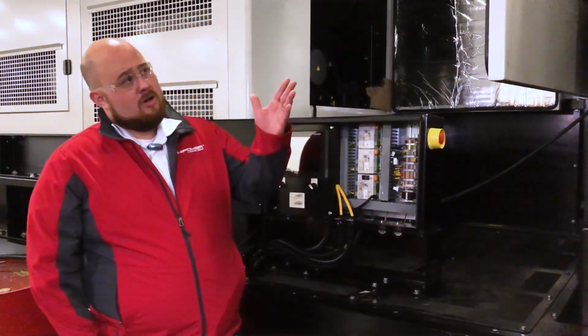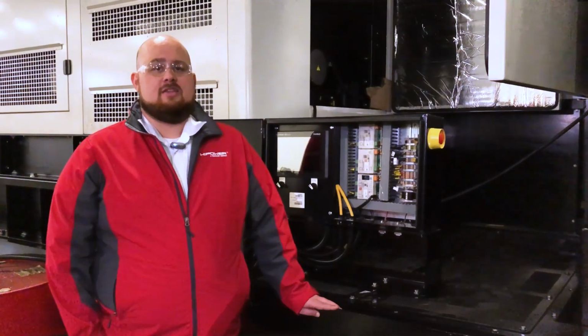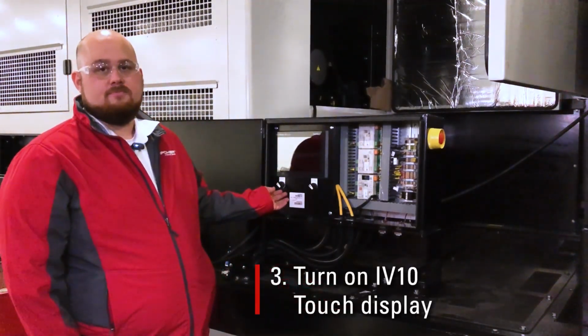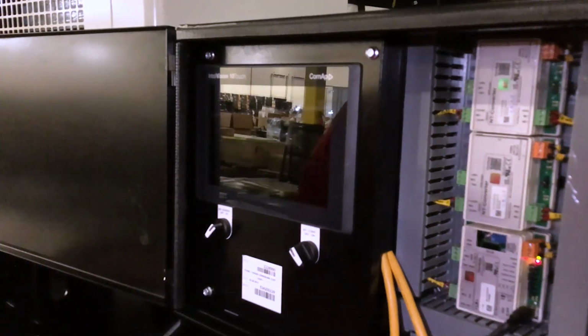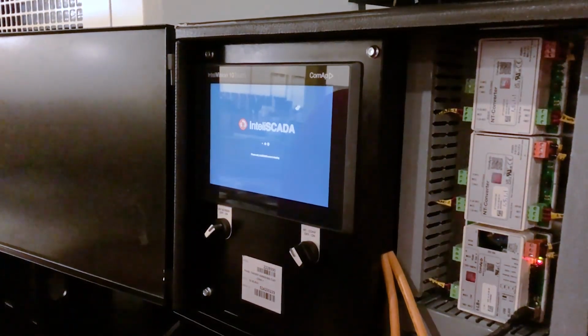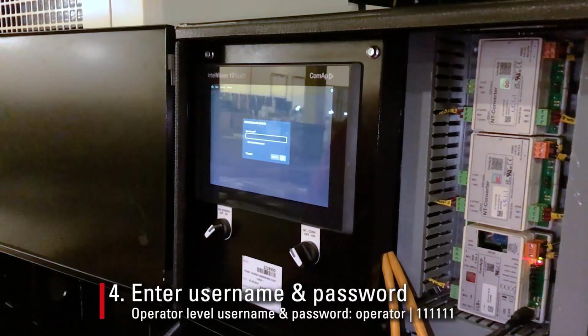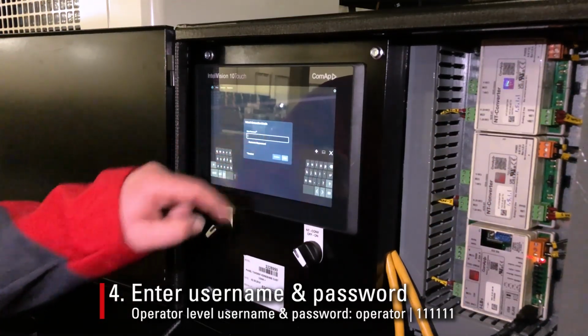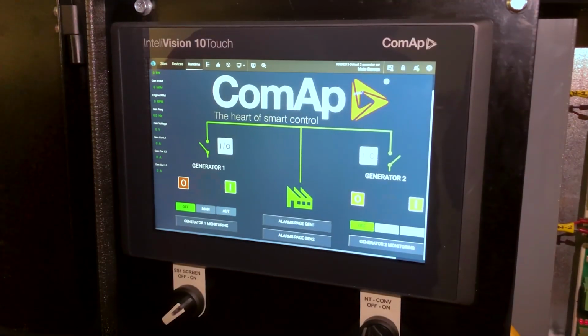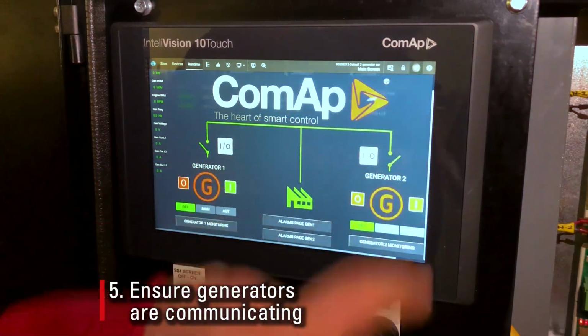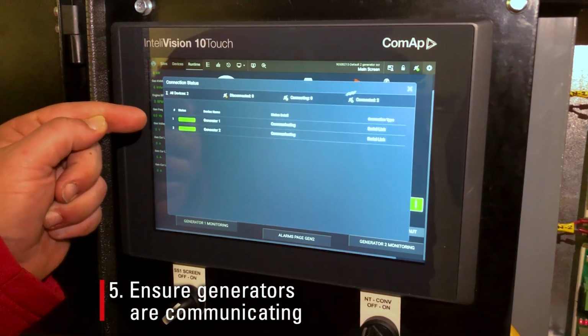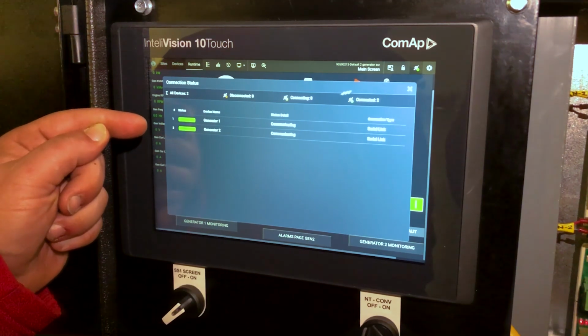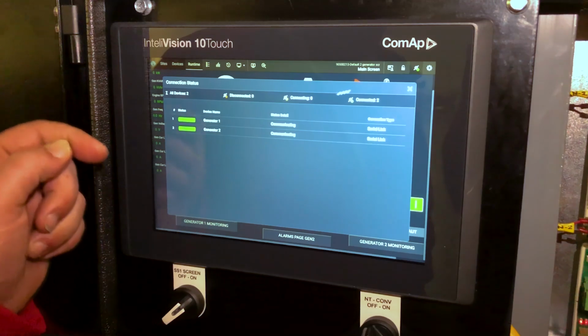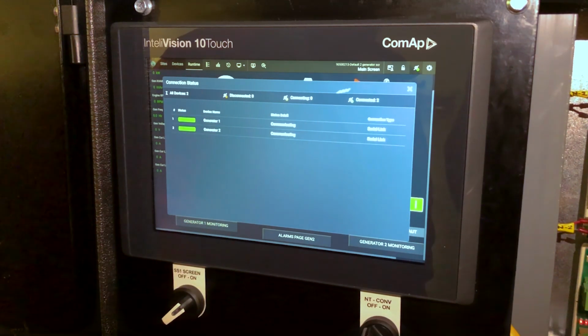After you've successfully powered up both controllers on the gensets themselves, the next step is to turn on the IV10 Touch display. Next, enter the username and password provided to you. Otherwise, you can enter the operator level username and password. The next step is to ensure all generators connected are communicating through CAN bus, which can be seen here. On the screen, you'll be able to view the connection status of the generators. You will want to ensure that every generator being used is displayed on this page and is shown as connected. In this case, we are only using a single twin pack, and we can see both generators are connected.